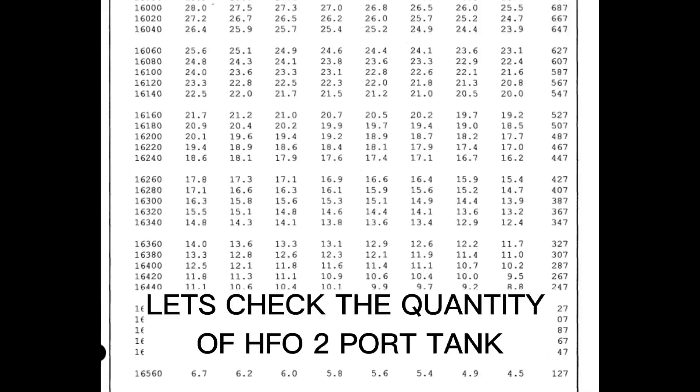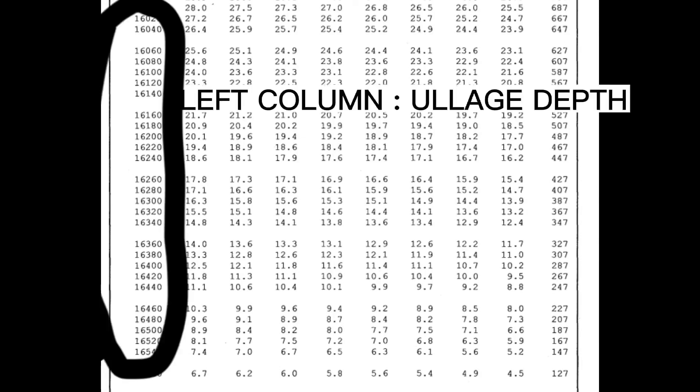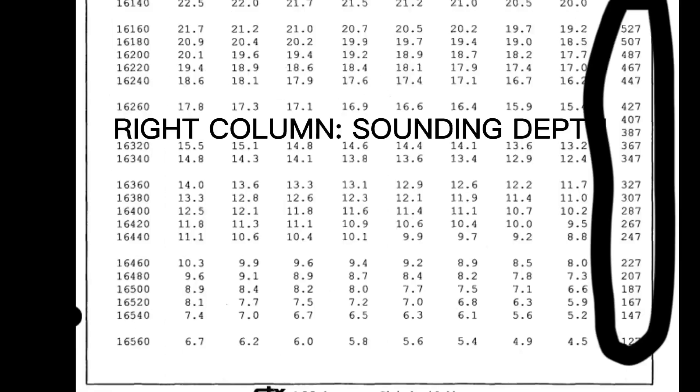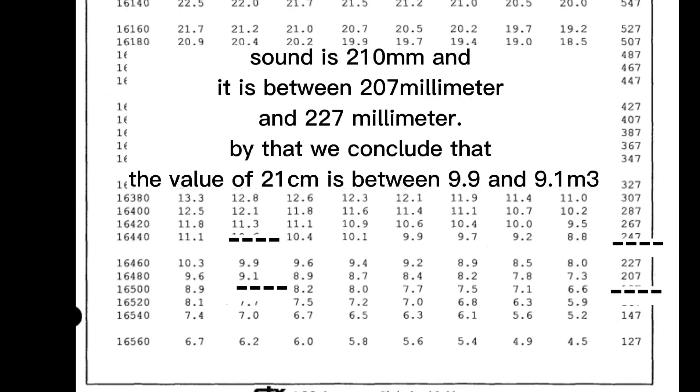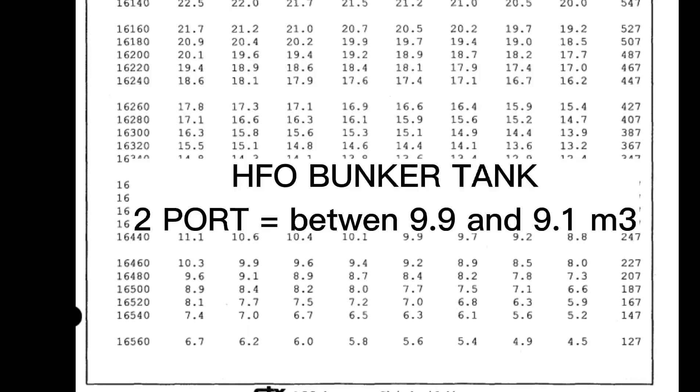Let's check the quantity of HFO 2 port tank. Left column ullage depth, right column sounding depth. Sounding HFO 2 port tank equals 21 centimeter. Sound is 210 millimeters and it is between 207 millimeter and 227 millimeter. By that we conclude that the value of 21 centimeters is between 9.9 and 9.1 cubic meters. HFO bunker tank 2 port equals between 9.9 and 9.1 cubic meters.